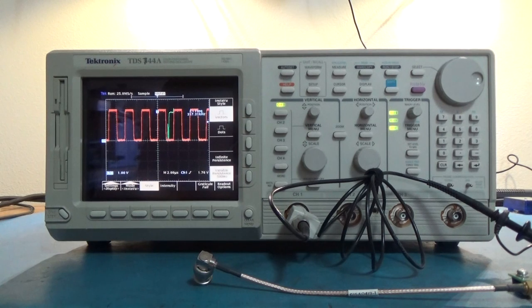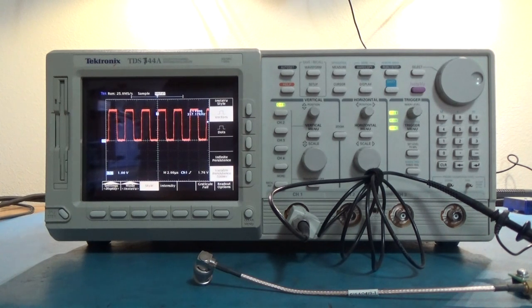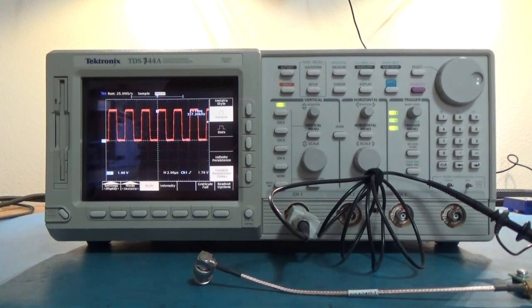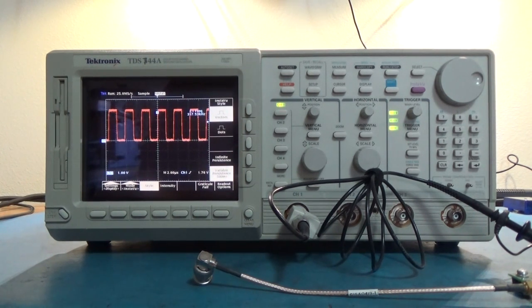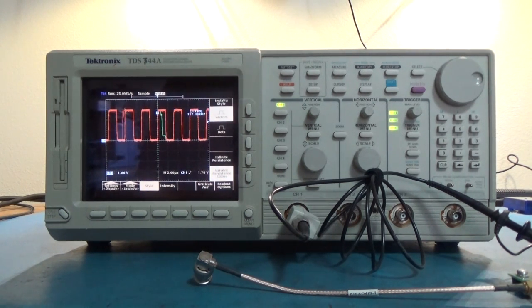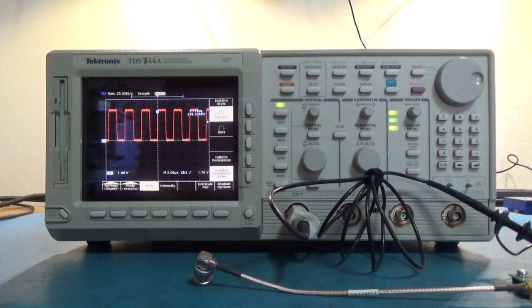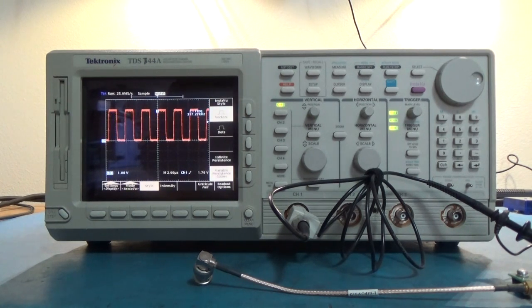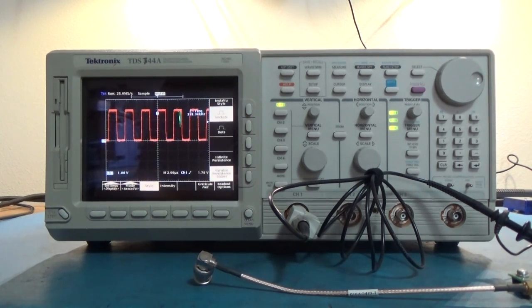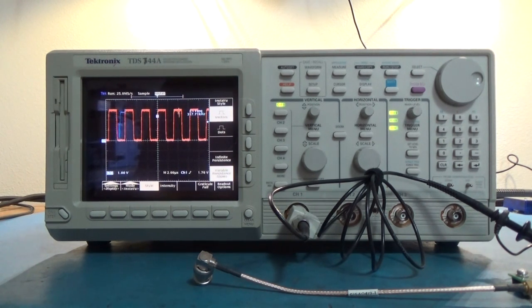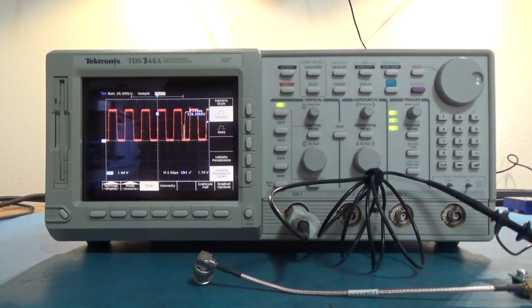LeCroy and Agilent didn't have anything. LeCroy immediately came out with something that kind of looked like it was doing this. But you had to know what the glitch was to trigger on. These scopes are sampling fast enough where they can actually accurately draw whatever they see. And what this is doing is Tektronix claims 400,000 times per second. It's updating a waveform database on screen.